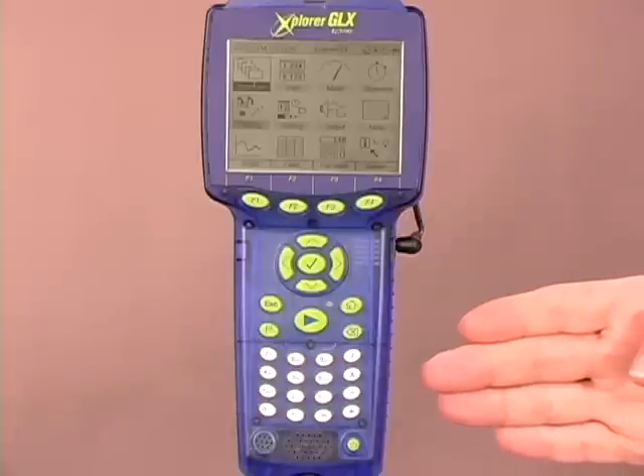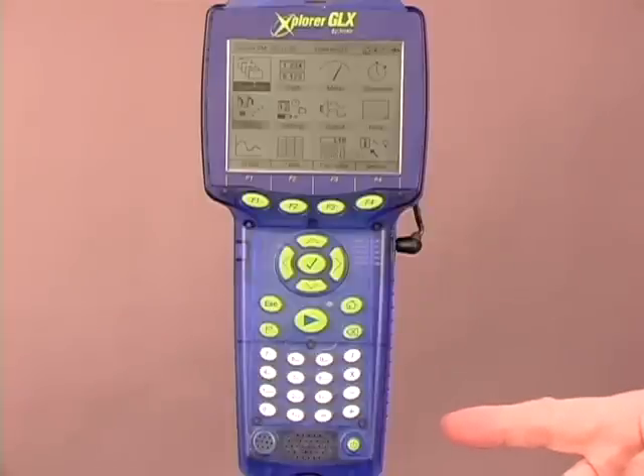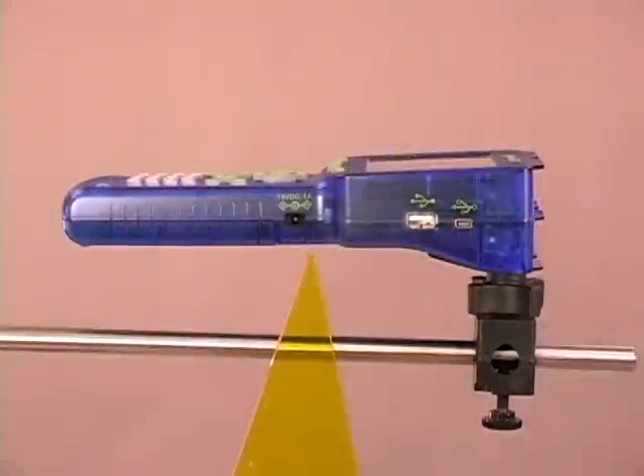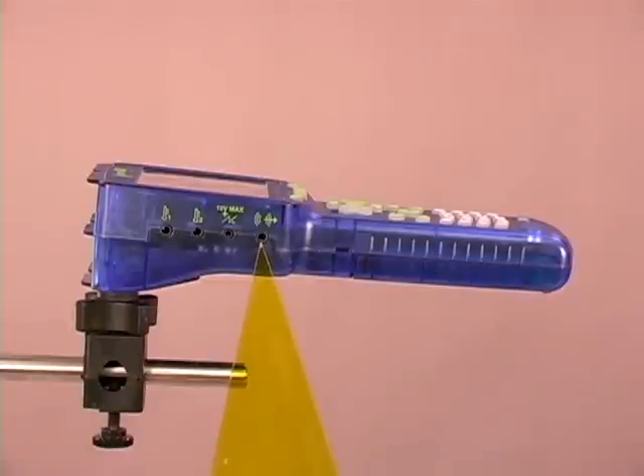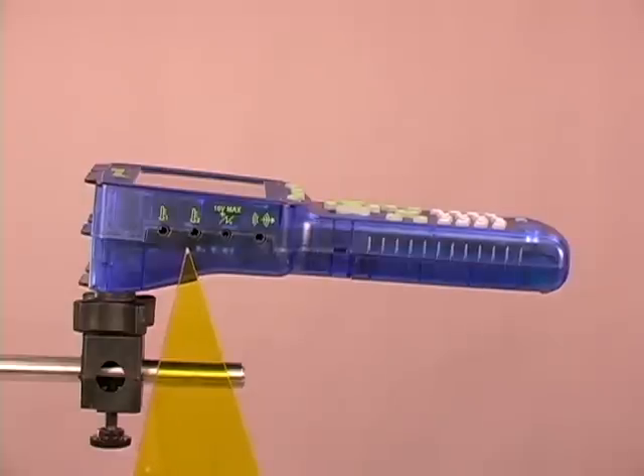We have the numerical function keys, which allow us to do calculations or numerical or text entry. At the bottom we have the power button, the speaker, and the microphone for built-in sound measurements. On the right-hand side we have the power connection, a USB port for connecting peripherals such as keyboards or printers, and a USB on the Go port which allows you to connect to a computer or additional peripherals. On the left-hand side we have a port for powered speakers with a dual function generator, a port for connecting the voltage probe, and two additional ports for connecting temperature probes.